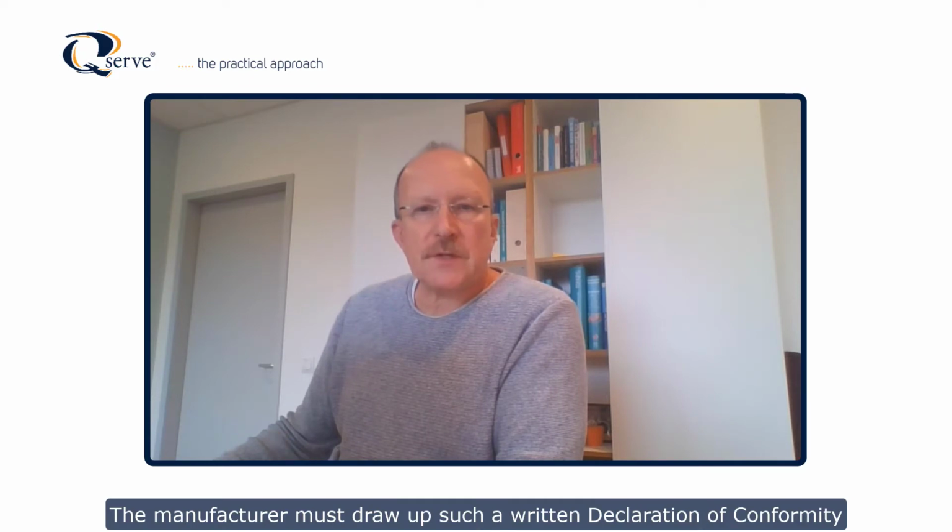is placed on the market in accordance with all applicable product legislation. According to Annex 2, 5 and 6 of the MDD, so Directive 93/42/EC, the manufacturer must draw up such a written declaration of conformity. The declaration must cover a given number of products manufactured. That is a challenge for several manufacturers.